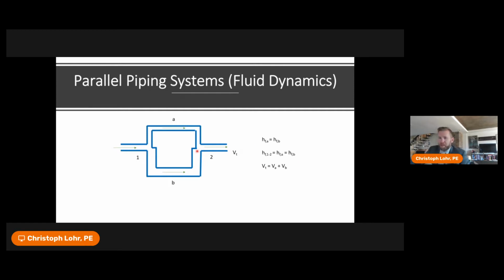But this is the part that I've noticed a lot of engineers seem to struggle with. And that is the head loss through segment A has to equal, in this system, the head loss through B. And the head loss from nodal point 1, where the system diverges, to nodal point 2, where the system converges, is also equal to that pressure loss of A through B.